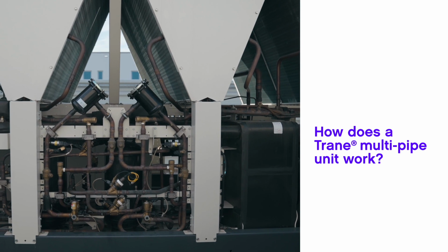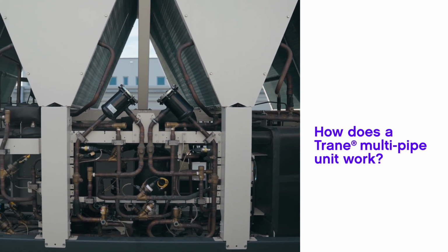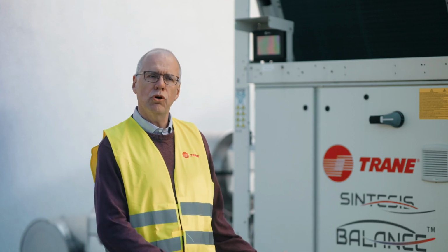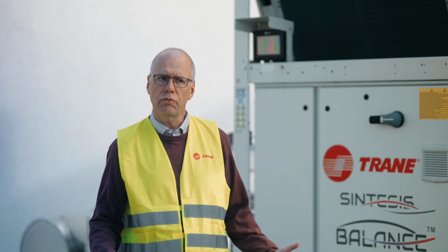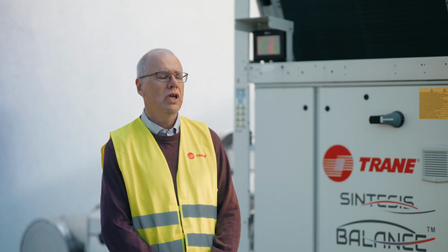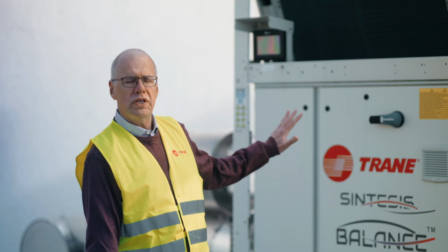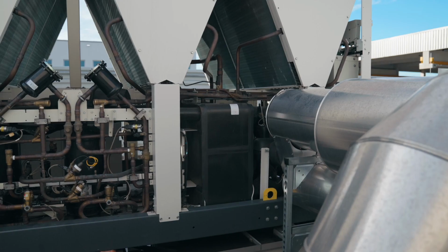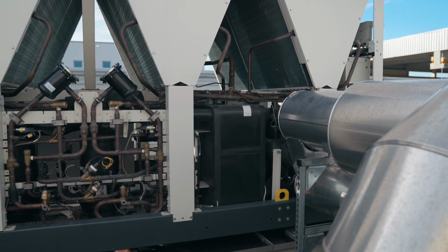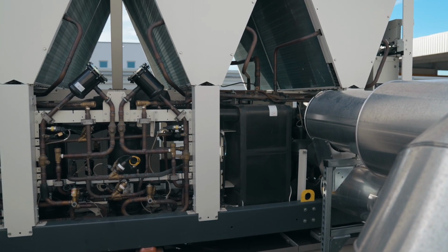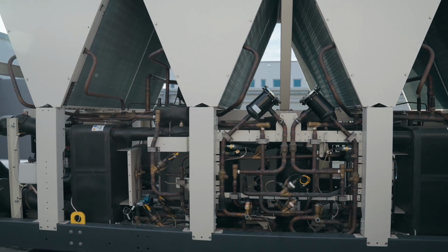So let's take the example in the industry. This unit can operate in heating mode, cooling mode, or heat recovery mode, and can combine the different modes. In fact, there are 3 heat exchangers on this unit. One of the heat exchangers is connected to the cooling side, the other one is connected to the heating side, and we have an air heat exchanger.